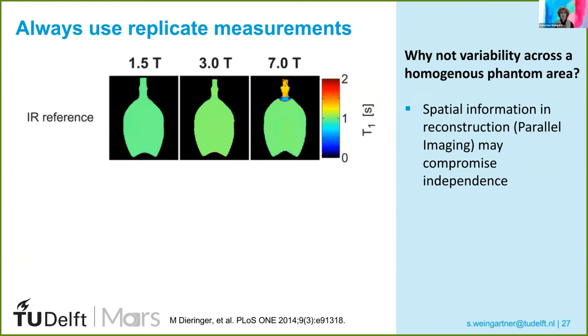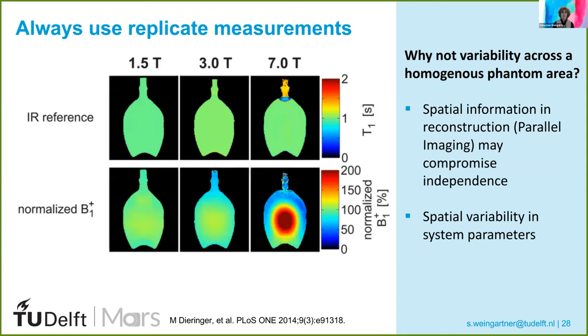You may wonder why we need replicate measurements in the first place. What if we put a lot of effort into designing a very homogeneous phantom? Can't we just use the spatial distribution of our measured values as a marker for precision? That's not a very good idea, because spatial information is often used in the reconstruction and therefore may compromise the independence between different measurement locations within the same phantom object. Even if this is not the case, many system parameters may be varying in the background, including the B1+ field or the B0 inhomogeneity.